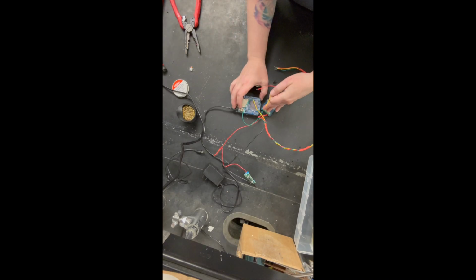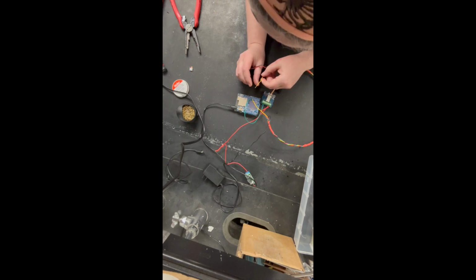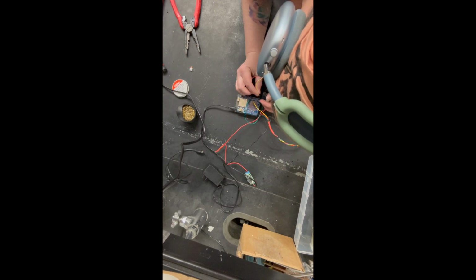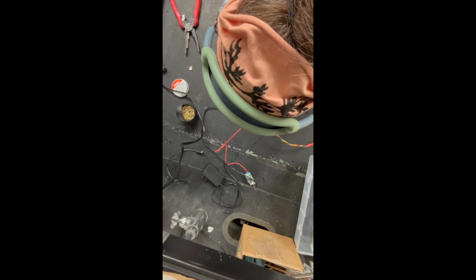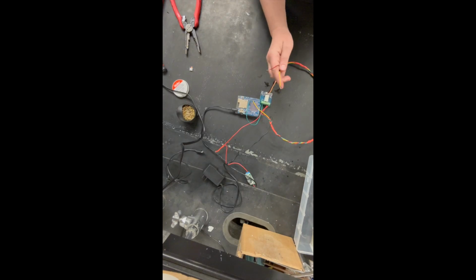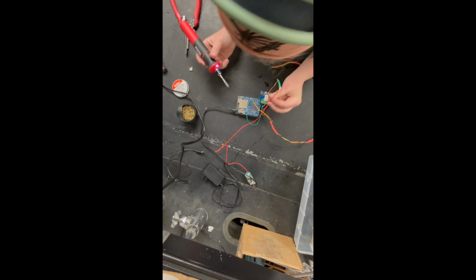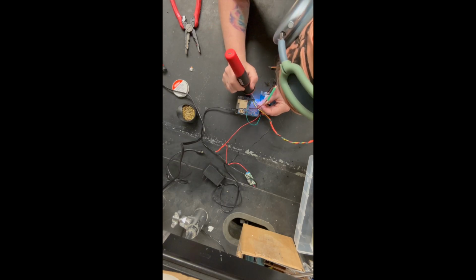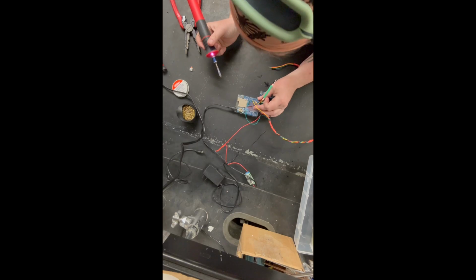My last communication cable is this yellow one coming from the 2-coil latching relay, and it is going to go into space number 7 on the data logger. Get that in place - this one's a little harder, it wants to spring out of that spot. Oh, and I haven't gotten any rosin on it, so I'm probably going to preload some solder on my soldering iron for this one, since it doesn't want to stay put. Put it in the space and go ahead and solder that joint.